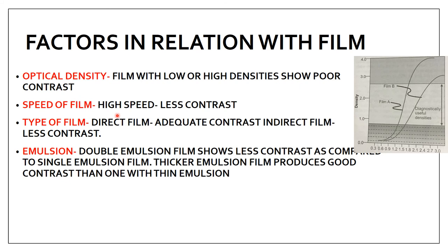The next factor is the speed of the film: if you are using a high speed film, the contrast will be low — inversely proportional. The next is the type of film, whether direct or indirect: a direct film shows adequate contrast, while an indirect film used with an intensifying screen shows less contrast. The next factor is emulsion: a double emulsion film shows less contrast and a single emulsion film shows high contrast. Also, a film with thicker emulsion produces better contrast than one with thinner emulsion.